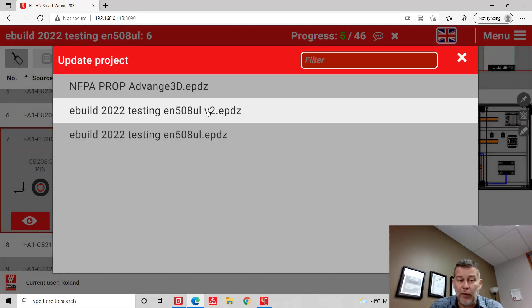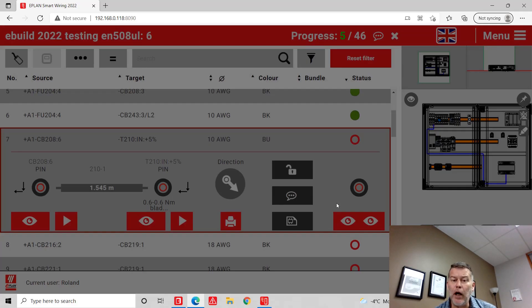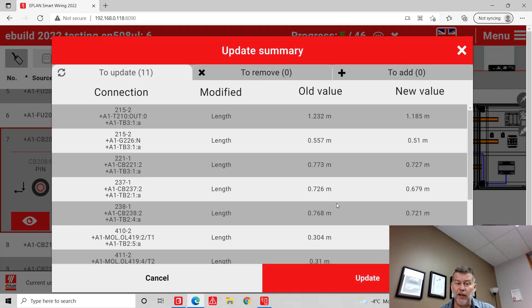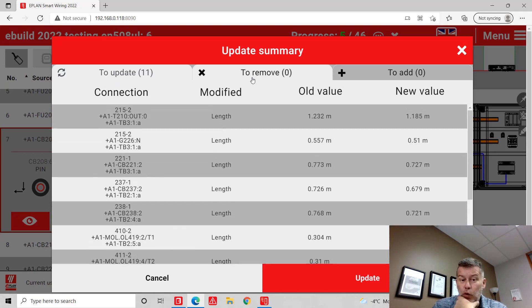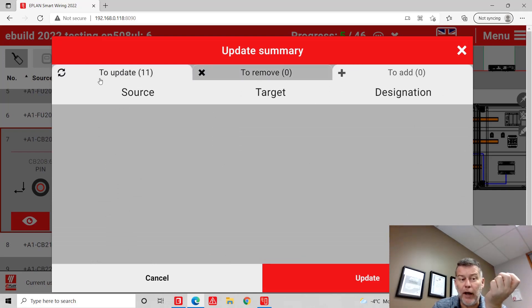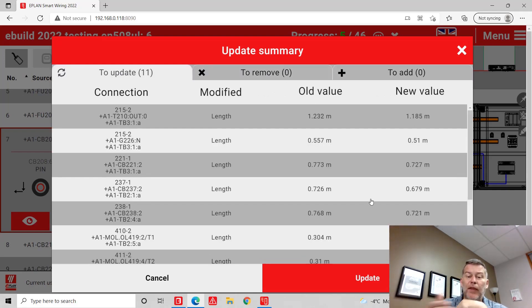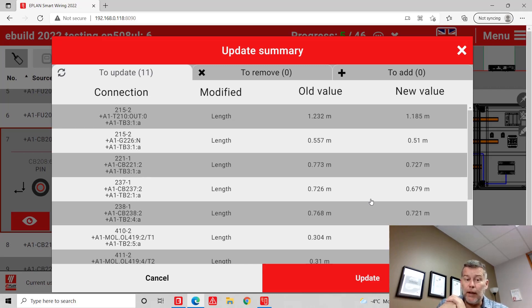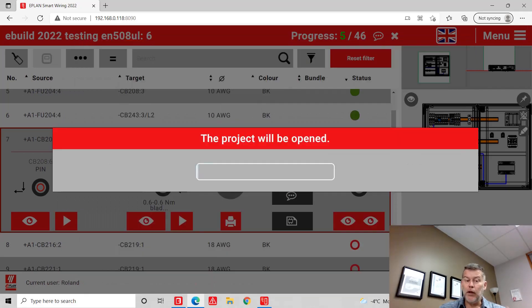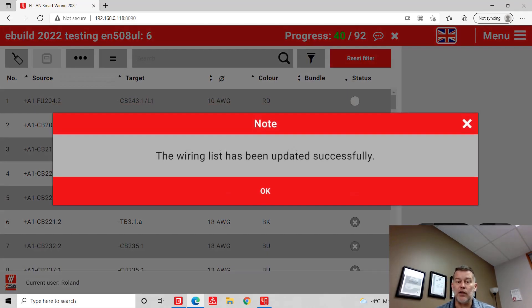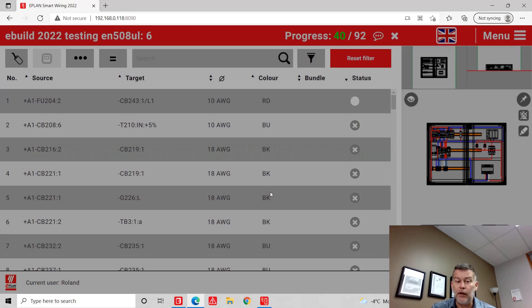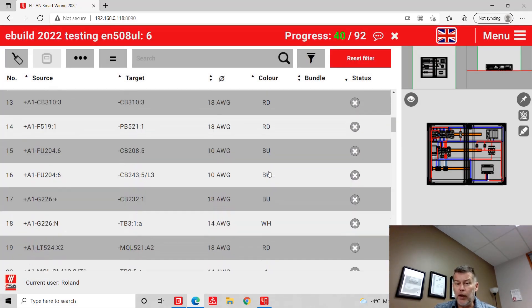maybe there aren't going to be any changes. If there are, you can see the values here. You can see the to-be-updated wires. To remove wires: none — I didn't touch them. To add: basically coming up with 11 updates. None of these wires have been really installed, so I can just update them. Now my project is updated — my five already-installed wires are not necessarily touched. The wiring list has been updated and I can go in there and work.